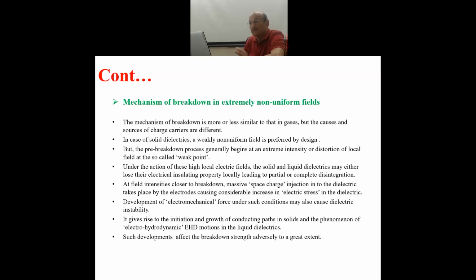So when you use open air, atmospheric air, that is not taken into consideration. But certainly when you use an enclosed chamber, SF6 gas, GIS, etc., you do attempt to remain within weakly non-uniform field conditions. But the pre-breakdown process generally begins at an extreme intensity or distortion of local field at the so-called weak point, as I just mentioned, in case of solid and liquid dielectrics. Weak points adversely affect solids and liquids too much.